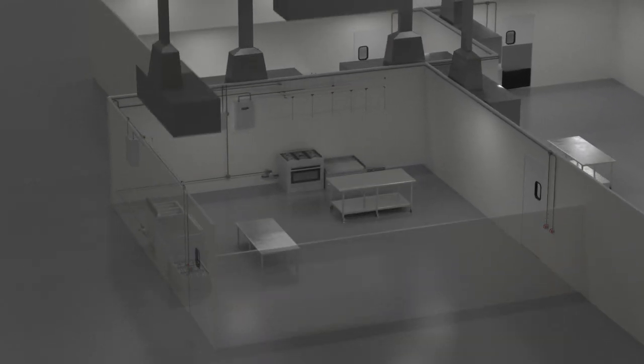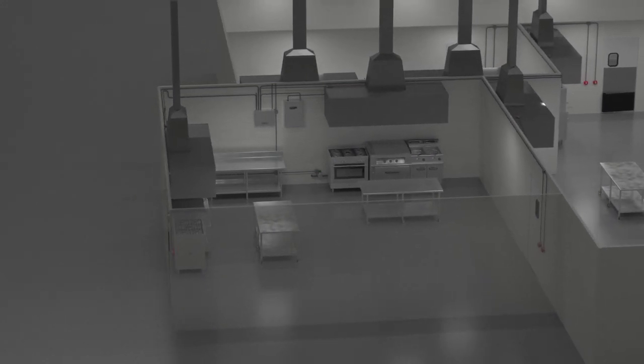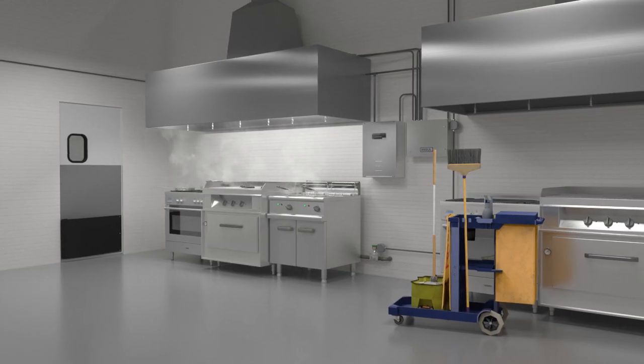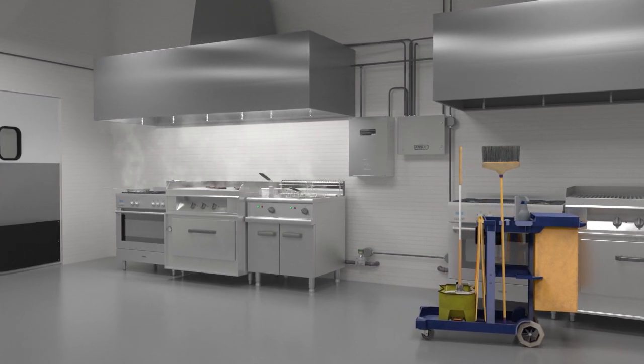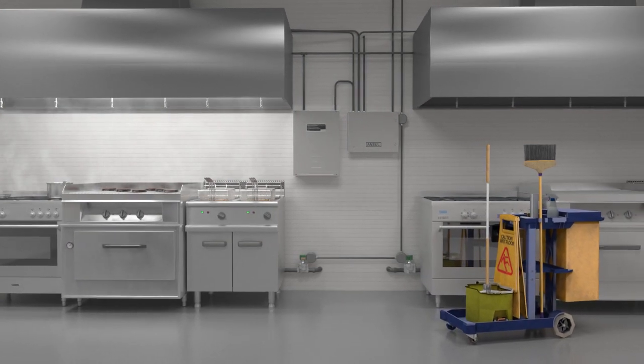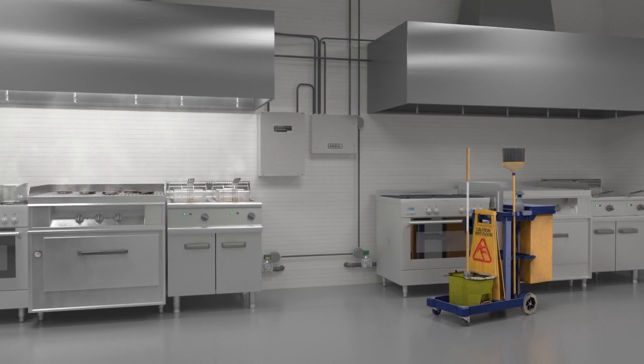RED technology is scalable, offering the convenience and cost effectiveness of monitoring multiple kitchens in one building and protecting more lineups with one system. It includes a cleaning mode feature that isolates selected detection circuits, allowing users to clean one hood while keeping others in operation. To assure continuous operation, it also has a timer that returns the system to its normal operating mode if the cleaning mode is not manually turned off within a set period of time.